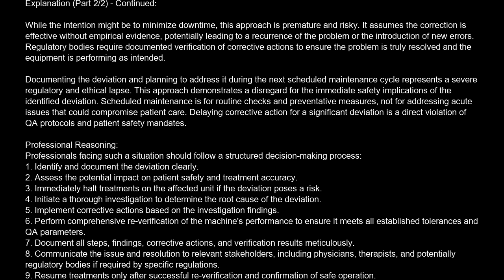Professional reasoning. Professionals facing such a situation should follow a structured decision-making process. 1. Identify and document the deviation clearly. 2. Assess the potential impact on patient safety and treatment accuracy. 3. Immediately halt treatments on the affected unit if the deviation poses a risk. 4. Initiate a thorough investigation to determine the root cause of the deviation. 5. Implement corrective actions based on the investigation findings. 6. Perform comprehensive re-verification of the machine's performance to ensure it meets all established tolerances and QA parameters.